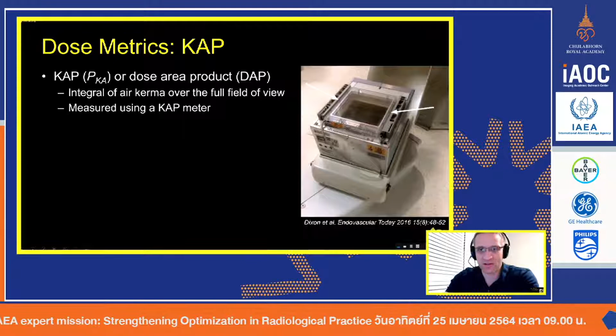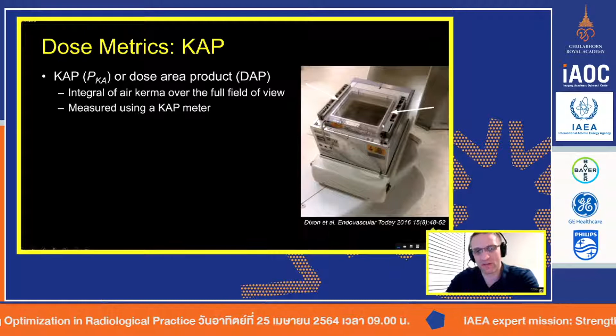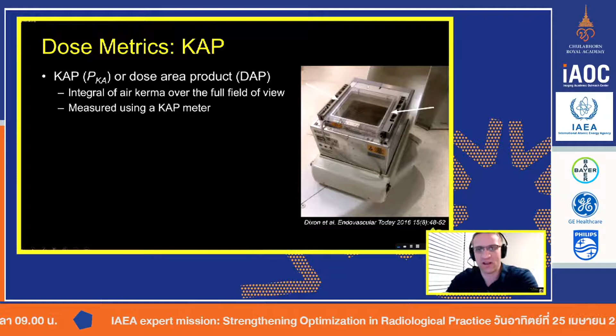So how do we do this? Well, there's an ion chamber, a KAP meter, that is on basically all of these, especially the interventional systems, but pretty much all of the fluoro units. It's on the collimator head. So this is the X-ray tube down here, and this is the collimator. So it's got the blades that you use for collimation, and then the KAP will sit right on the outside.